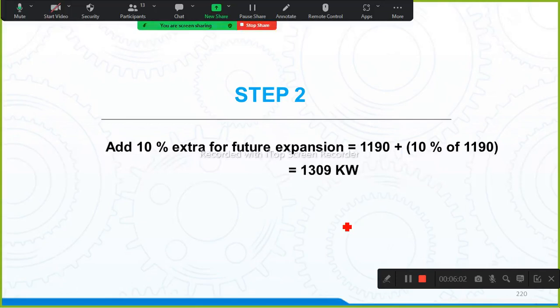Because in future if some 1 or 2 kilowatt or 5 kilowatt load is changed, you can't replace the existing transformer, because no one is going to purchase a transformer second hand. So whenever you plan for the present, plan according to your future requirement also. Step 2, add 10% extra for future expansion, that is 1190 plus 10% of 1190, which is equal to 1309 kilowatt total load.